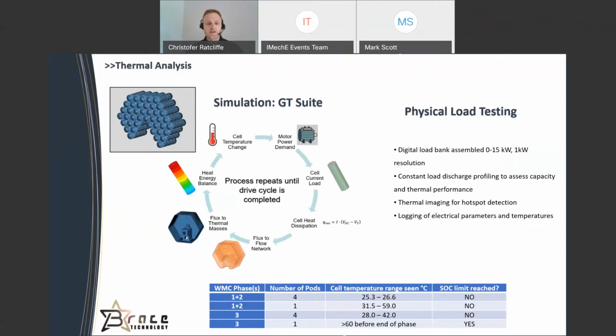When we run those phases on one single pod, which is the main use case and flexibility of the PowerPODs, again we're getting a temperature range at different points from 31 to 59 degrees. Again, that is under our specified upper limit. But in WMTC3, as we suspected, on one pod we did get problems - there would be some serious issues with thermal activity. And with four pods, we were actually capable of using four pods in emergency situations.